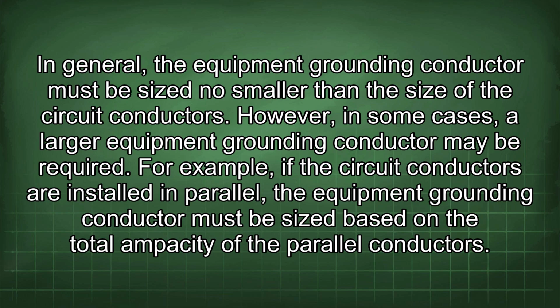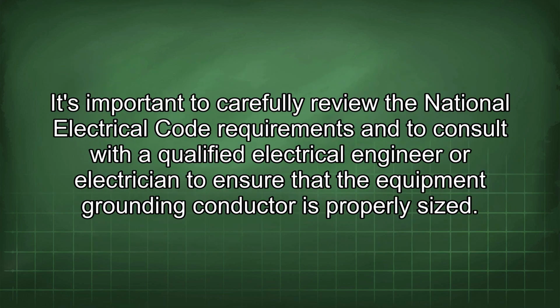In general, the equipment grounding conductor must be sized no smaller than the size of the circuit conductors. However, in some cases, a larger equipment grounding conductor may be required. For example, if the circuit conductors are installed in parallel, the equipment grounding conductor must be sized based on the total ampacity of the parallel conductors. It's important to carefully review the National Electrical Code requirements and to consult with a qualified electrical engineer or electrician to ensure that the equipment grounding conductor is properly sized.